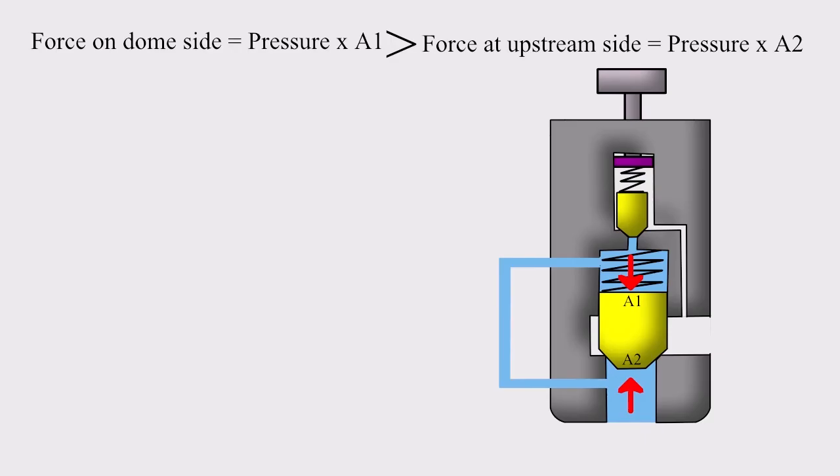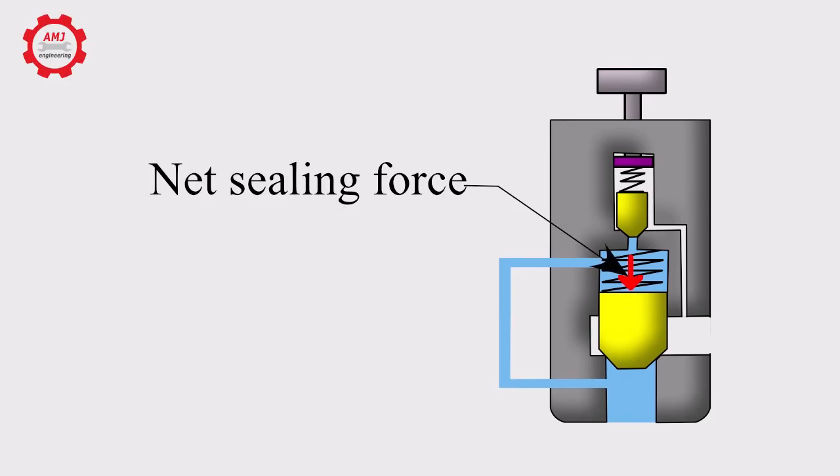The area of the piston on which fluid force is acting is larger in the dome than it is on the upstream side. The result is a larger force on the dome side than the upstream side. This produces a net sealing force.